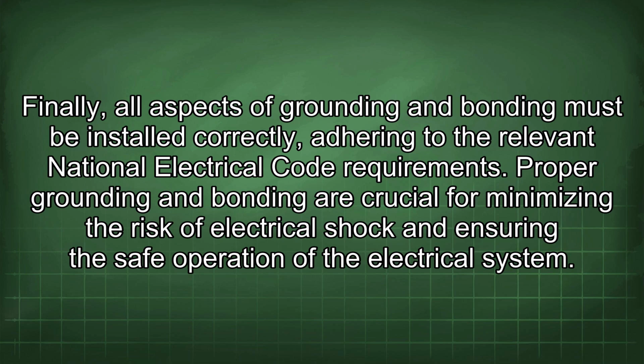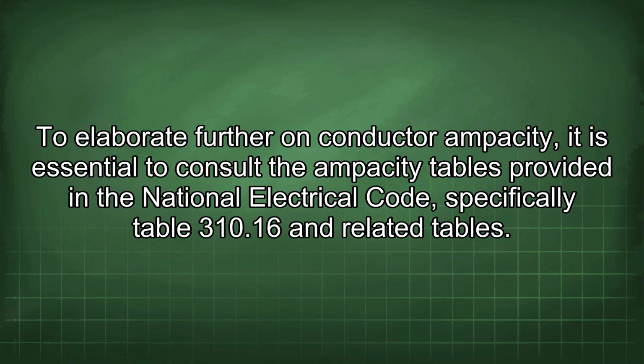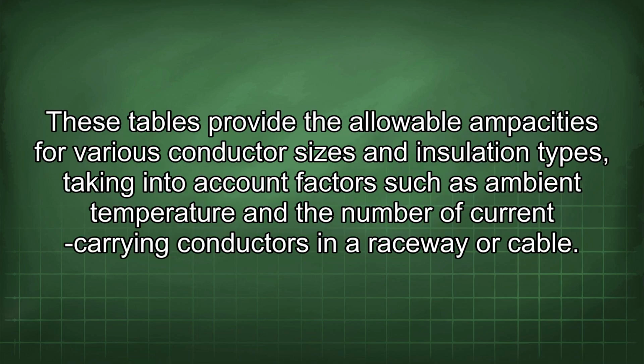Finally, all aspects of grounding and bonding must be installed correctly, adhering to the relevant National Electrical Code requirements. Proper grounding and bonding are crucial for minimizing the risk of electrical shock and ensuring the safe operation of the electrical system. To elaborate further on conductor ampacity, it is essential to consult the ampacity tables provided in the National Electrical Code, specifically Table 310.16 and related tables. These tables provide the allowable ampacities for various conductor sizes and insulation types, taking into account factors such as ambient temperature and the number of current-carrying conductors in a raceway or cable.